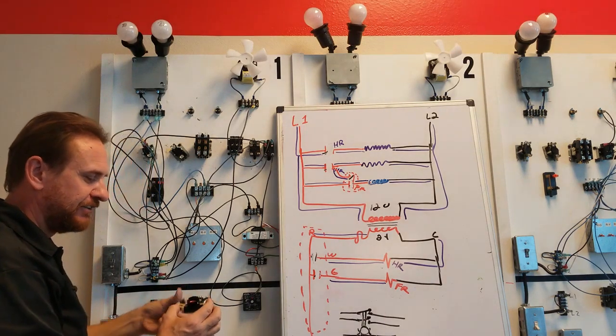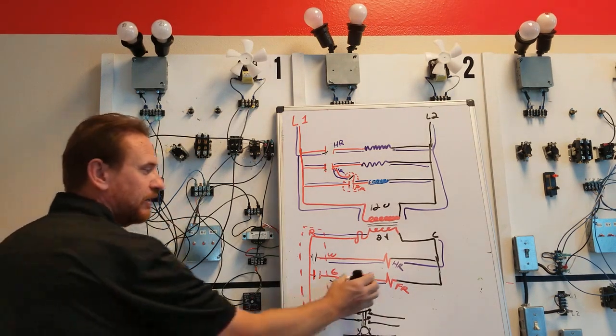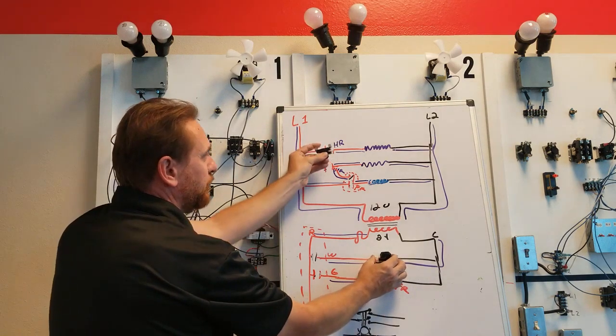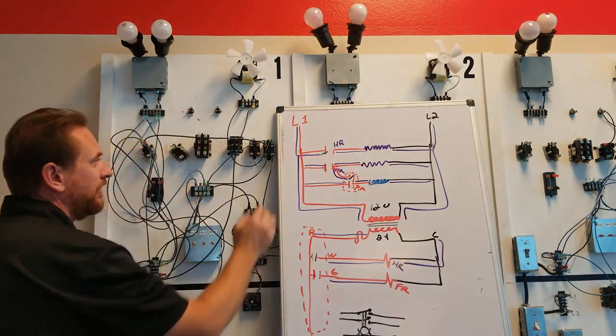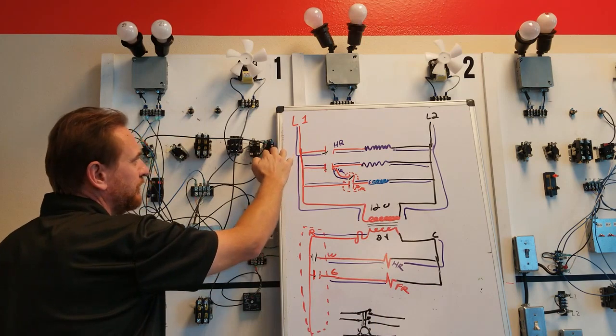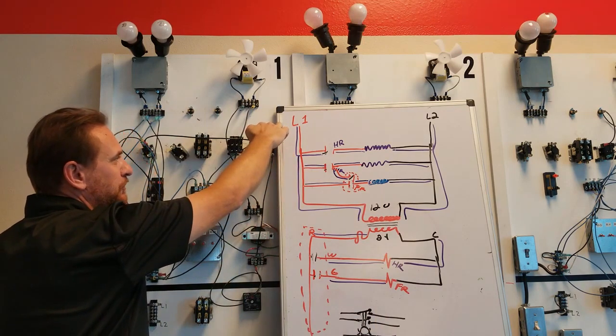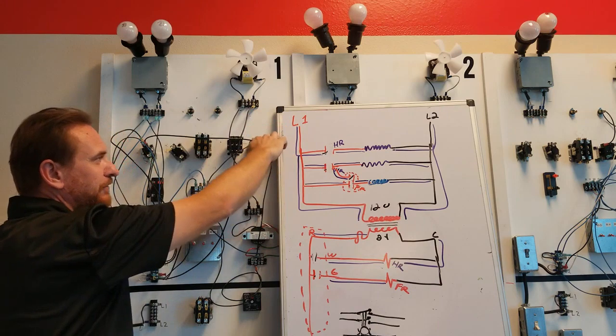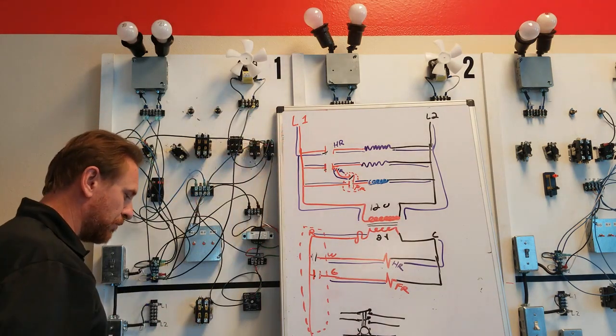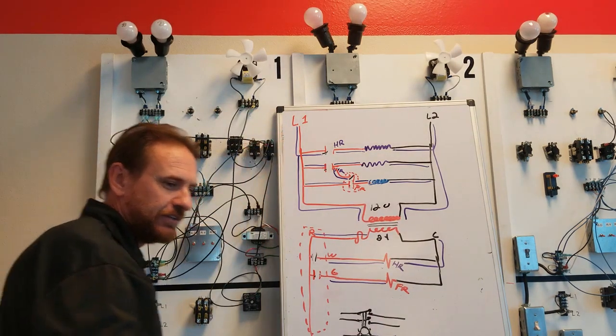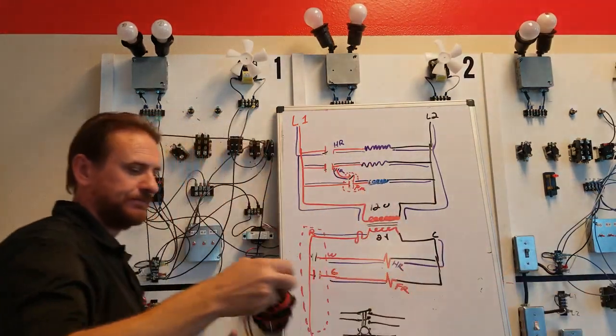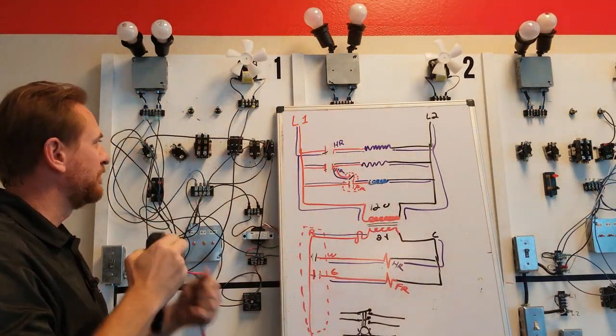Low voltage side, don't get it mixed up with the high voltage side. Low voltage down here, high voltage switch up here. On this fan relay, here's my low voltage side. High voltage normally open, high voltage normally closed. Three wires, it's a switch. If you want to know how that switch works, you can grab a meter. Here's one beside it. We don't know what it means.